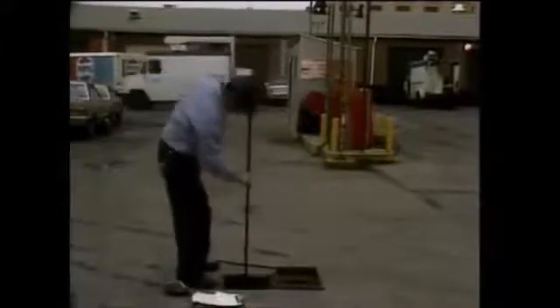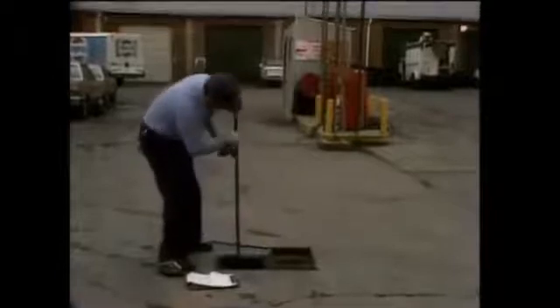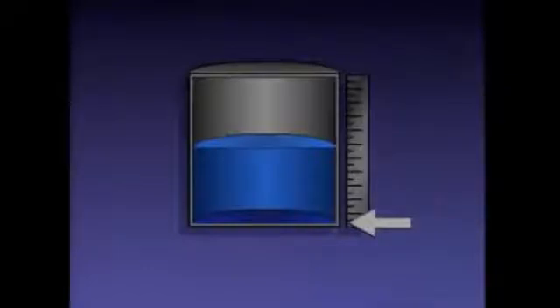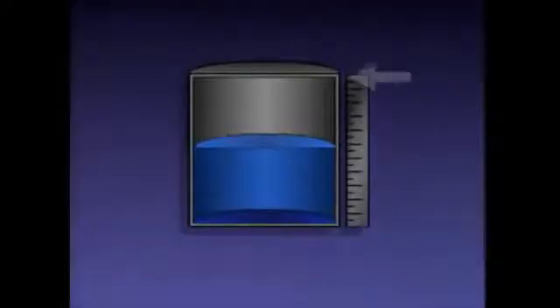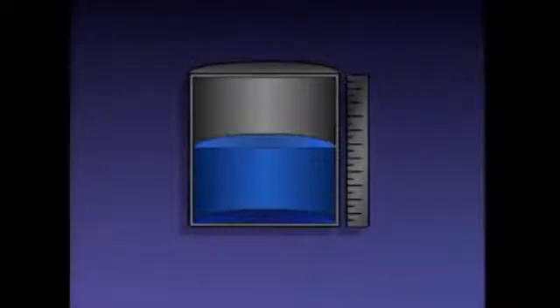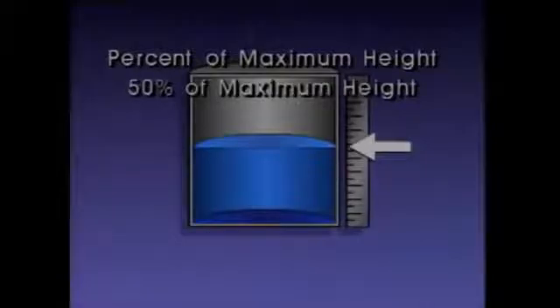The last process variable we'll discuss is level. Level can be defined as the position of a surface above or below a fixed reference point. For instance, if the reference point is at the bottom of the tank, measurements are taken from the bottom to the surface, indicating how much of the tank is filled. If the reference point is at the top of the tank, measurements are taken from the top to the surface, indicating how much of the tank remains to be filled. Another way the level in a tank can be expressed is as a percent of maximum height — for example, if the level is at the halfway mark, we can say the level is fifty percent of maximum height.